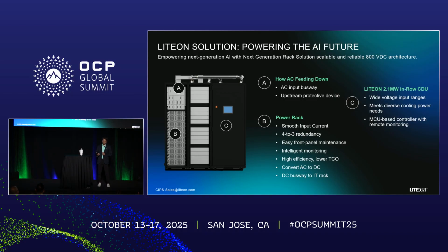I introduce to you our total solution for this next generation AI cluster. It features a high efficient 800 volt DC, 1 megawatt power rack with up to 4 to 3 redundancy, and it allows the user to do maintenance and upgrading from the front panel. It also features a lot of safety from the AC bus to the DC bus, because now we're trying to transmit 800 volt DC.